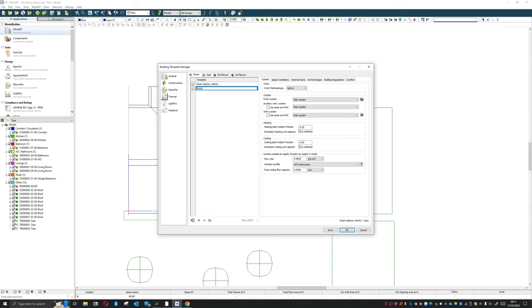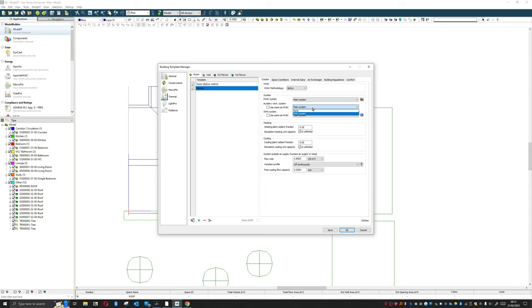So we can add a template - we tend to follow the room group types we set up earlier, which is why this can be very useful. Let's do the kitchen first. On the first tab we have our system - we haven't set up our systems yet, but the HVAC system is what's going to apply the heating or cooling to the space. For the auxiliary ventilation system, if we don't have a fan system supplying air we can set this to none. For domestic hot water, if it's the same as the boiler we'd say main system, but if it's a different system such as direct electric we would set that up separately.